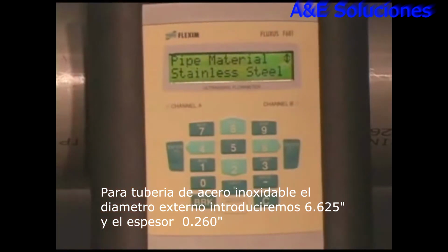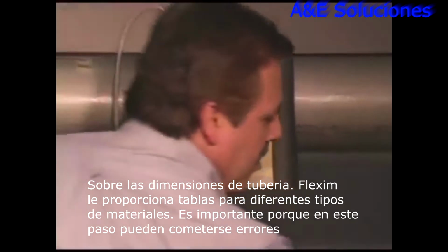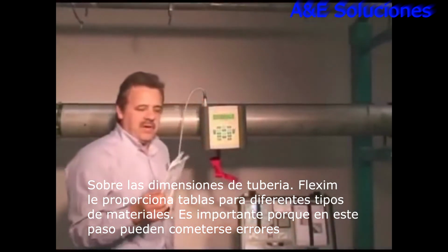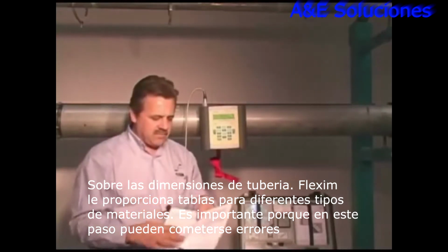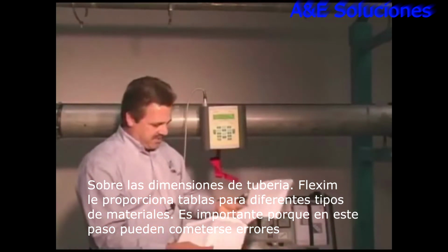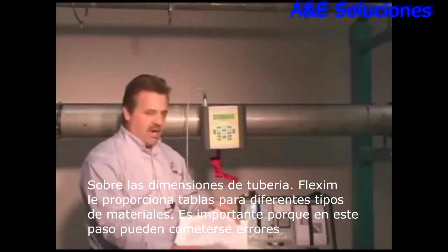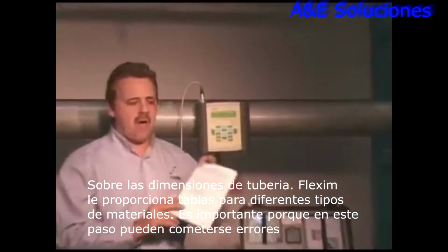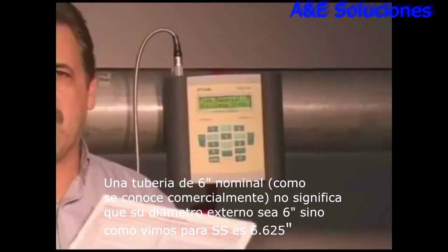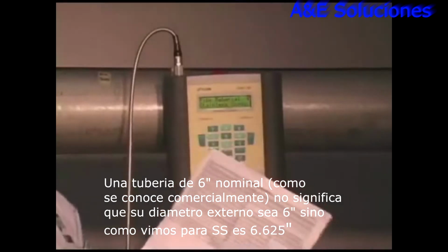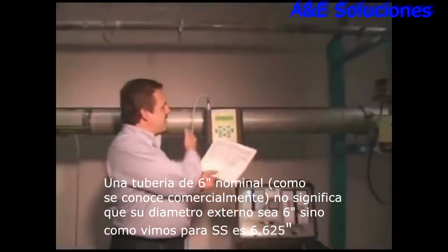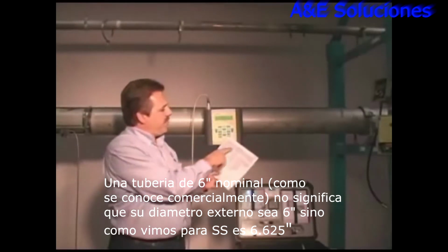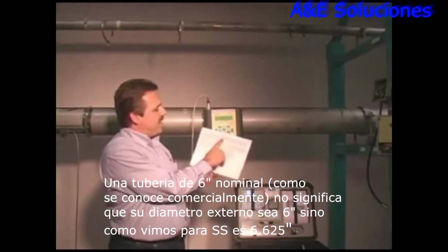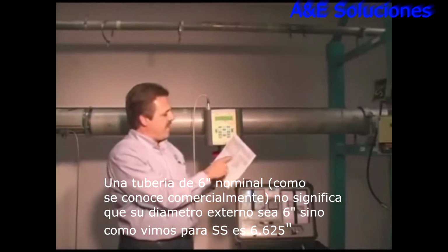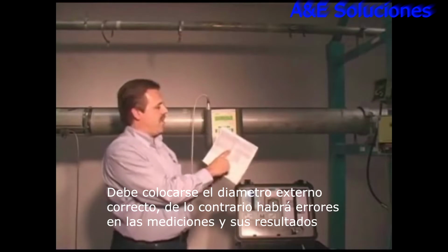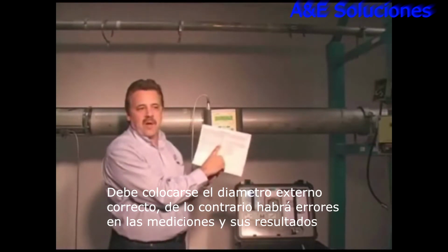Now if I could just talk a little bit about pipe dimensions. You'll find on the inside panel of the meter a pipe chart, and there will be pipe charts for steel pipes, stainless pipes, Hastelloy, ductile iron, copper, etc. Now, this is one place where the user can make a mistake, and so I want to spend just a little bit of time on this. This is a 6-inch pipe, nominally. If you look at the nominal size for a 6-inch pipe, it says OD 6.625, and if this were a standard wall pipe or a Schedule 40 pipe, the wall thickness is 0.280.